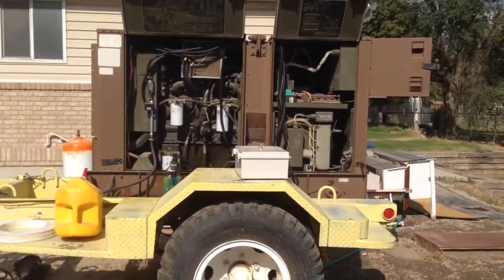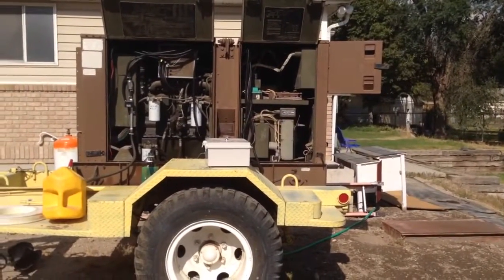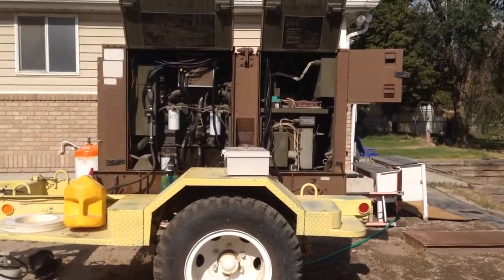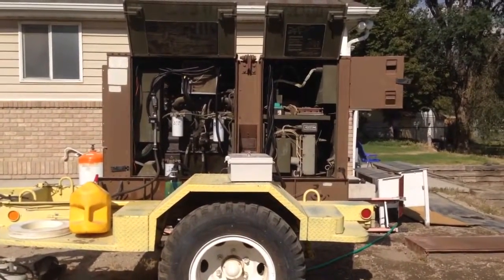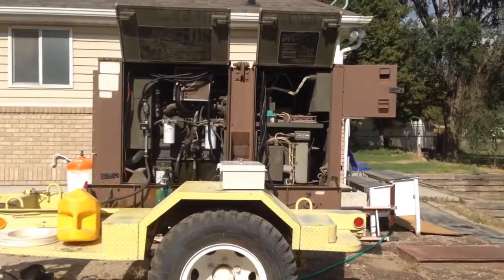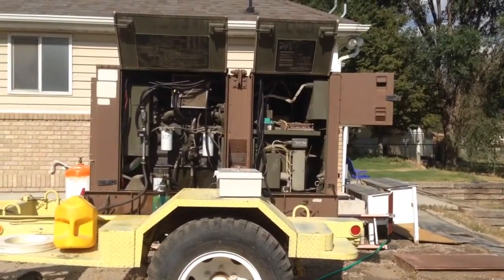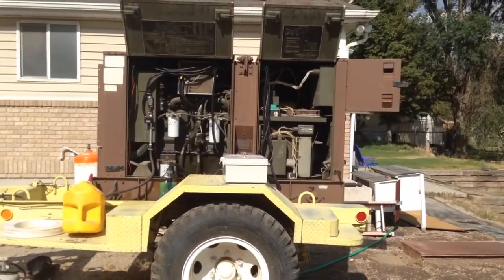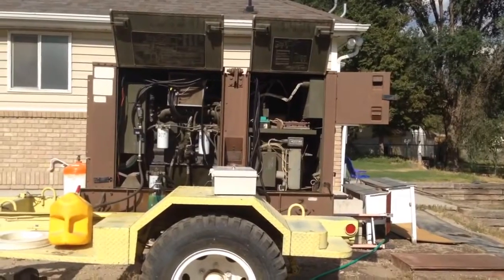Natural gas and diesel, number one, cost. Cost for natural gas to a gallon of diesel equivalent. Obviously, natural gas is a gas form, not liquid form, so there's a comparison. But a gallon of diesel equivalent of natural gas is about 60 cents per gallon. So it's just a fraction of the cost of diesel fuel. The other benefit is runtime. So if you're running, let's say, a 50-50 natural gas to diesel mixture, you'll get double the runtime on the same amount of diesel that your generator already has now.